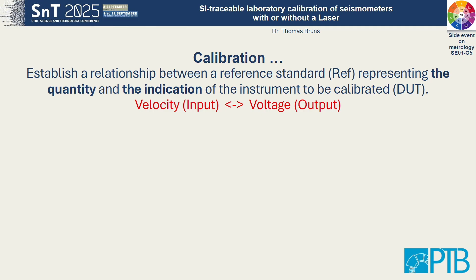First of all, a very short introduction. It was already told to you by my preceding presenters. What is a calibration? It makes a relation between a reference standard representing the quantity and the indication of the instrument. For seismometers, the input is typically a velocity that we somehow have to realize. We also talk about the realization of the unit. And then the voltage output of the seismometer. I'm deliberately taking off the digitizer here. We also work on digitizer calibration, but that's a completely different topic.